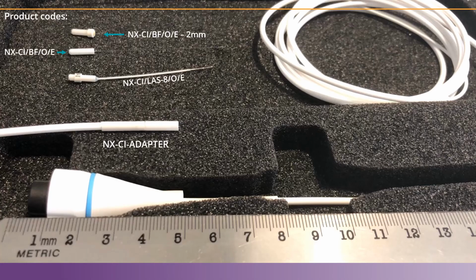The top two sensors are variations of a bare fiber chronic implantable or CI sensor. The top one is a 2 millimeter long one, and the middle one is the standard length, which is 60 millimeters or 6 centimeters. The bottom sensor shown here is the LAS8 CI sensor, and the fourth product is the CI adapter. You can also see the standard connector for the adapter here with the blue ring around it to match the OxyLite system.